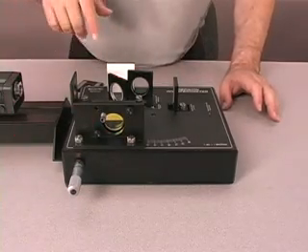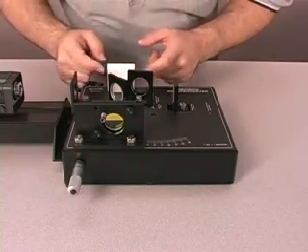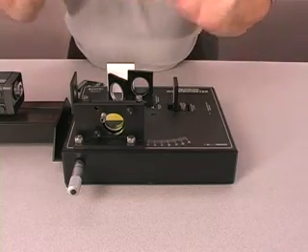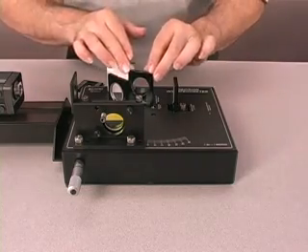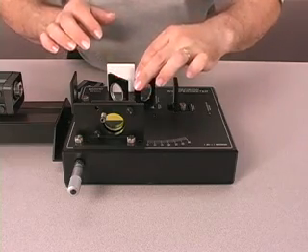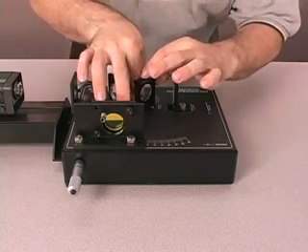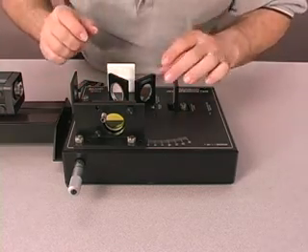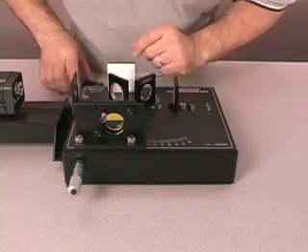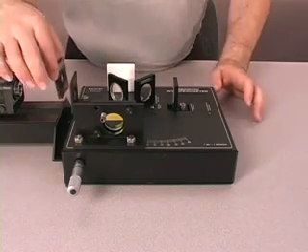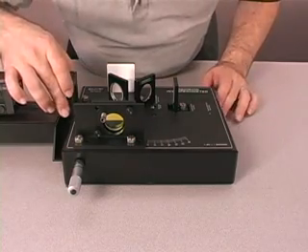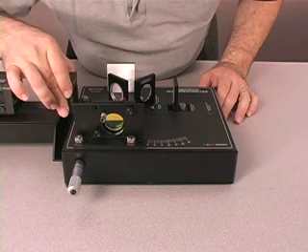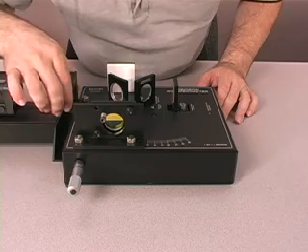Now, as you get close, you're going to actually start seeing a little bit of wavering and that means you're trying to see a fringe pattern. But what I'm going to have to do now, and this is counterintuitive, is move my compensator lens back into place to make sure that I'm properly compensating for the path of the beam. I'll check my alignment and then bring my lens back into play and adjust it until the beam is right back where it was before.